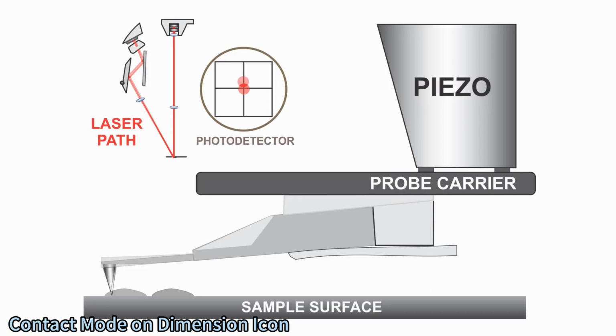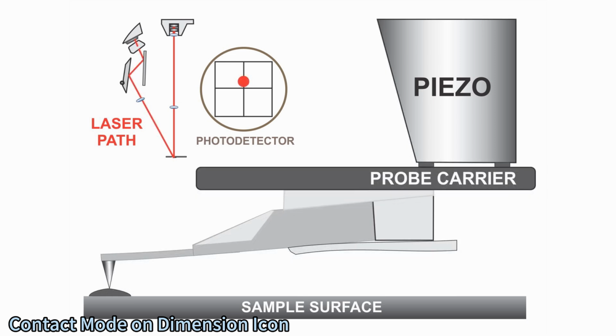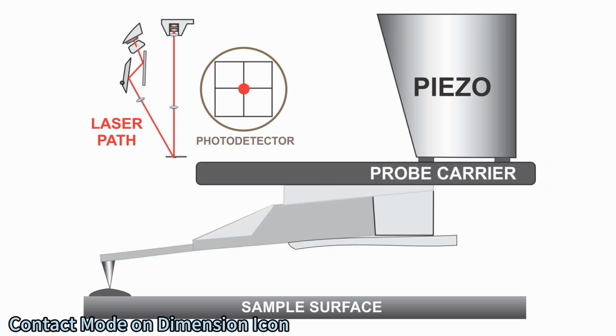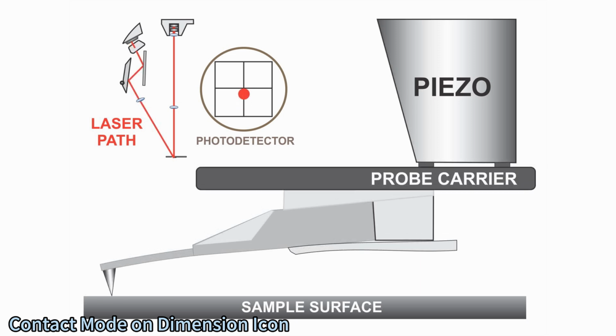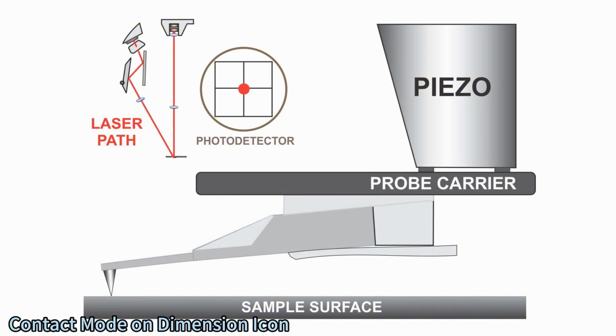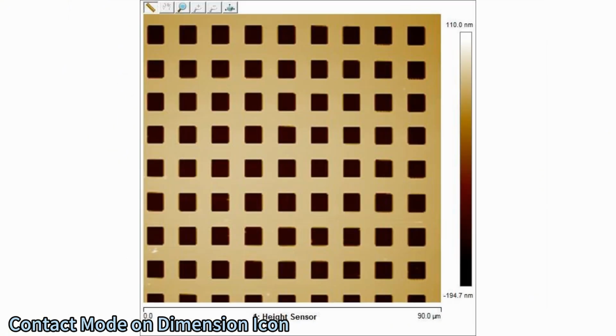As the probe encounters elevations or depressions in the sample surface, the feedback loop through the controller forces the scanner to react to the deflection change and restore the set point value. This loop is constantly being updated and maintained by the controller while the piezo is rastering the tip across the sample one line at a time. The result is a topographic map of the sample surface.